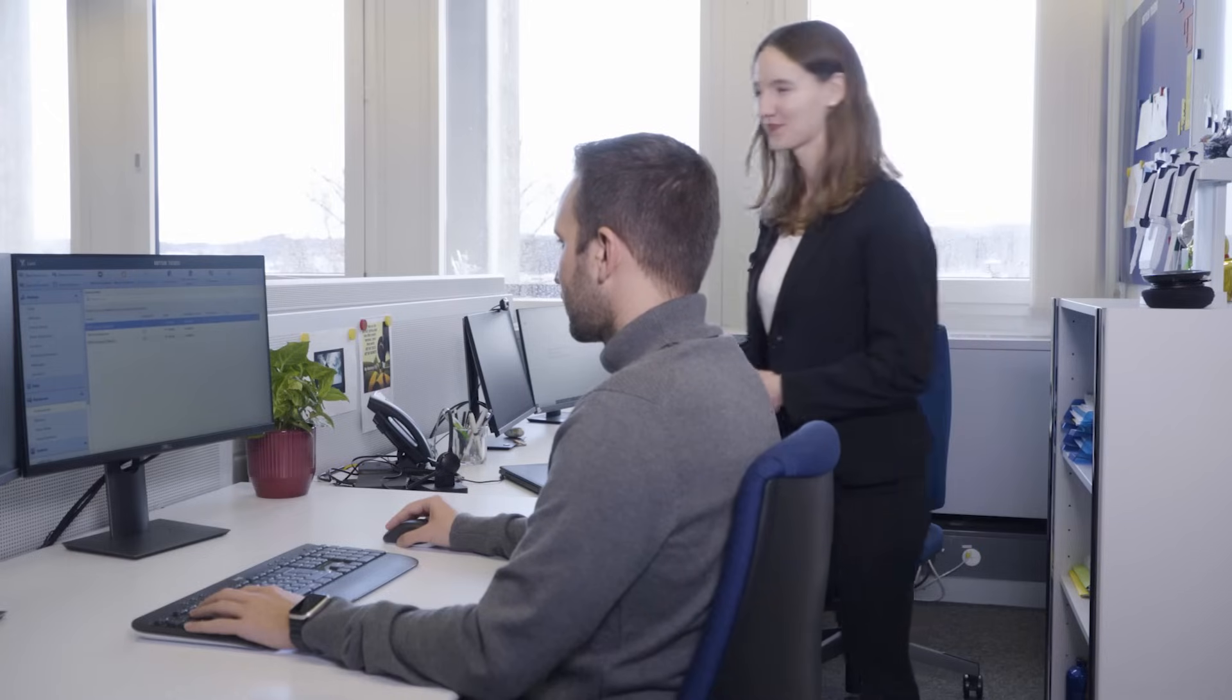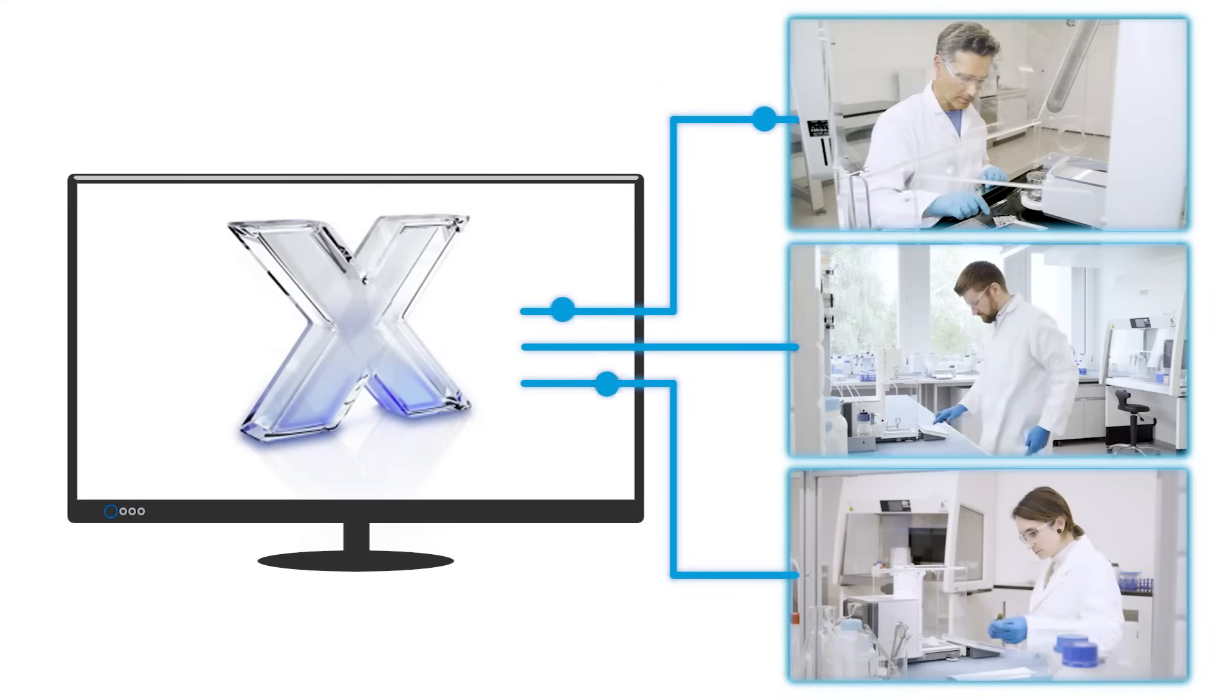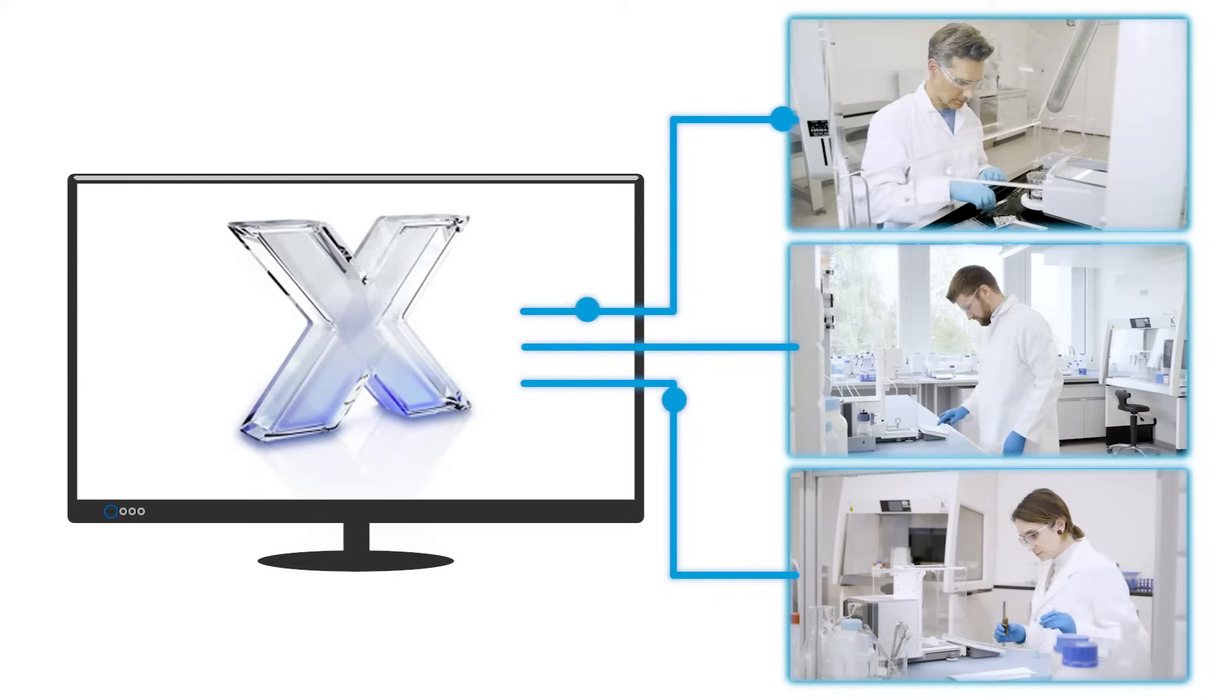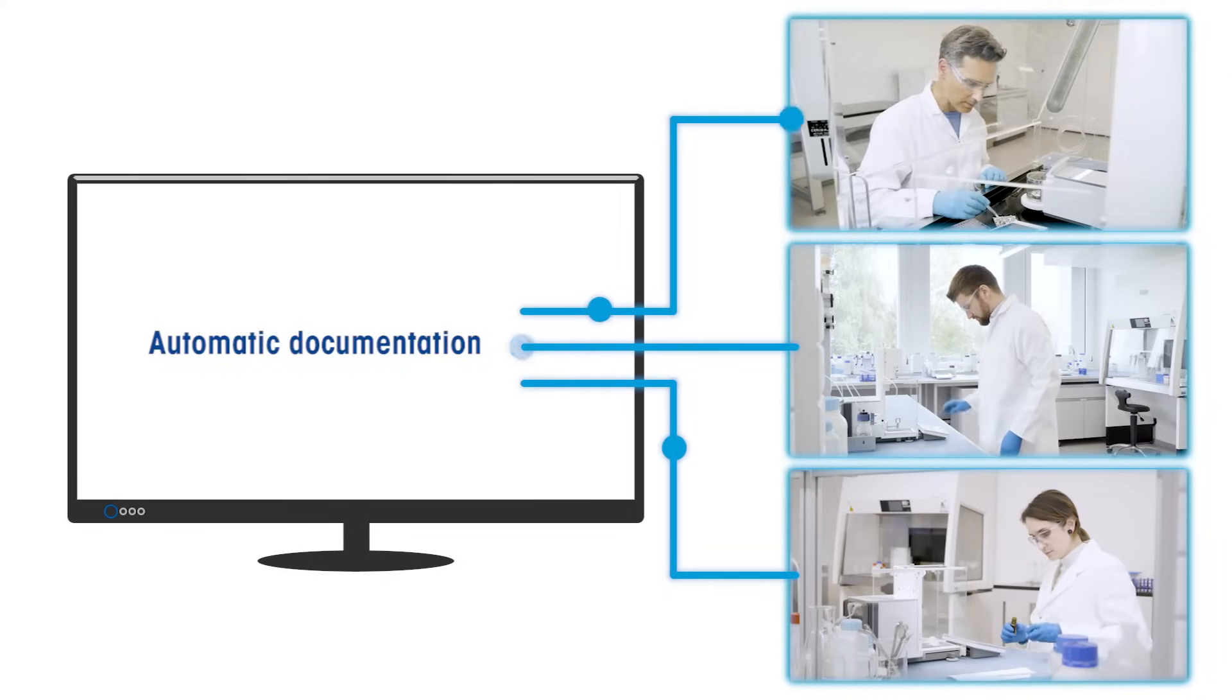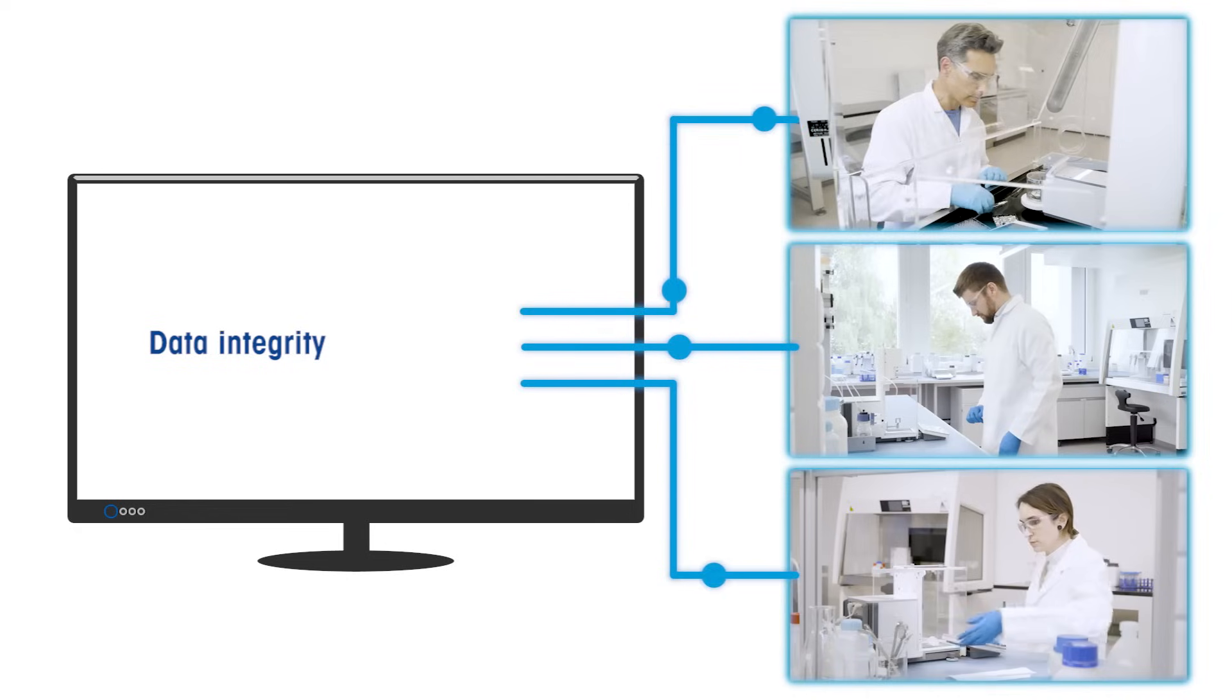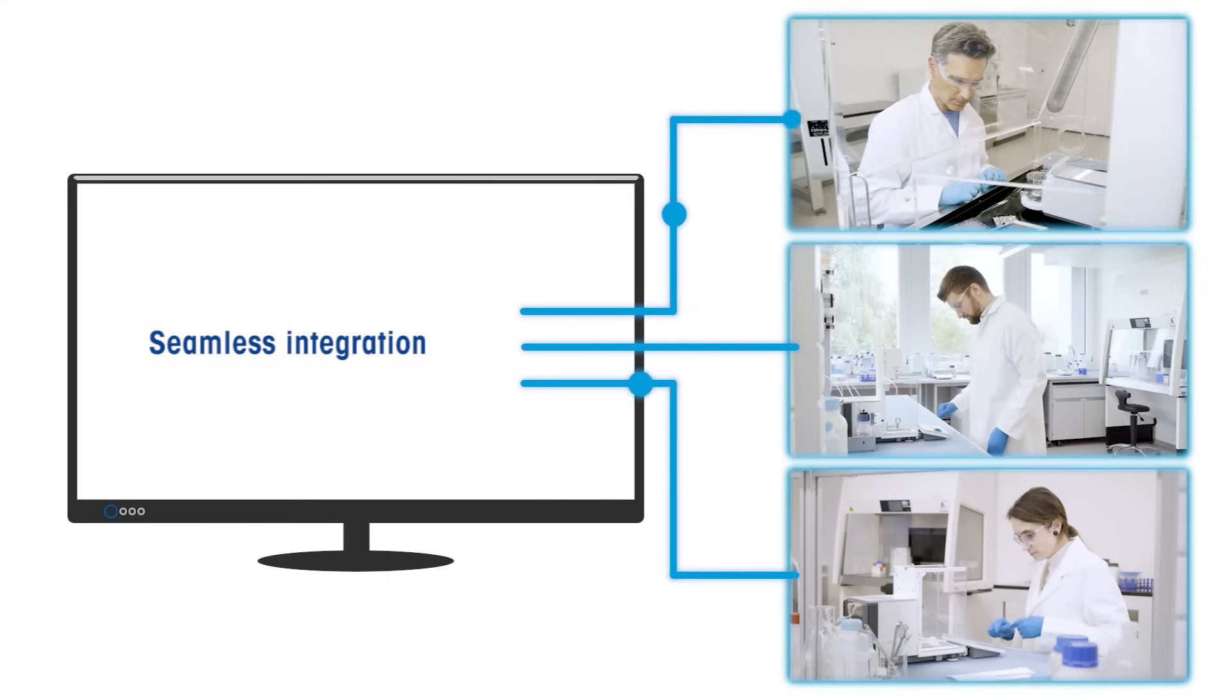You can also run LabX, our state-of-the-art laboratory management software, on the XPR balance. LabX is another breakthrough that will increase your lab productivity through workflow automation and electronic data management. It ensures full data traceability and data integrity according to 21 CFR Part 11 and reduces the complexity of managing multiple lab instruments. Of course, it can also be integrated into your LIMS and other systems.